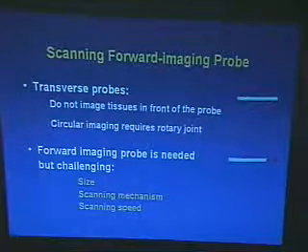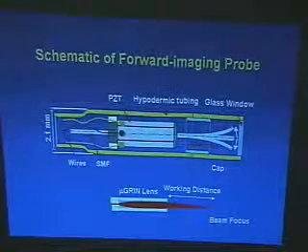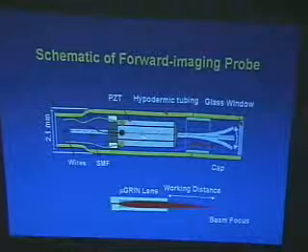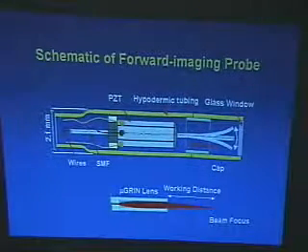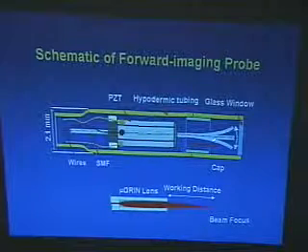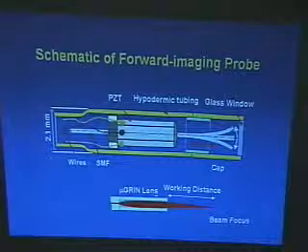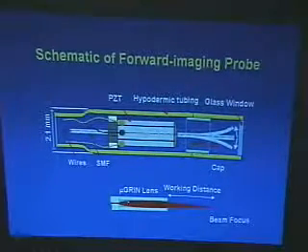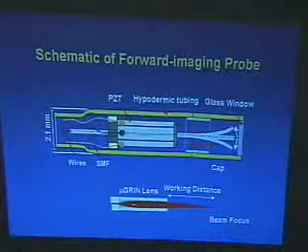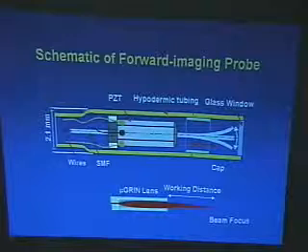How are we going to do that? And to keep the entire size small, catheter size small. Here is another approach we're currently developing: using a PZT piezoelectric actuator to move a very tiny focuser, or micro imaging probe. This micro imaging probe includes a single mode fiber, and then we can thermally fuse this micro imaging lens to the single mode fiber.